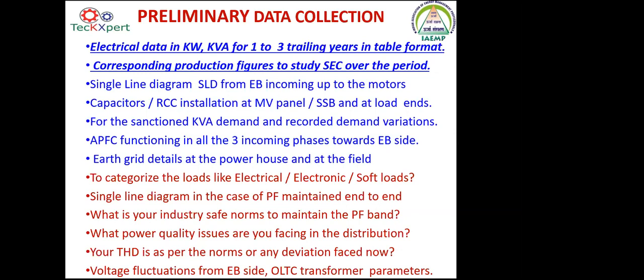Another aspect is, apart from the capacitors, the reactor-coupled capacitors installation, where it is done at the SSB, at the powerhouse, and what is done at the load end. At the load end, to be specific, the APFC functioning in all the incoming three phases is more important, because now the industry has gone to a slightly economical mode of 1 CT only. If they go for a 3 CT mode of measurement, especially in controlling the automatic power factor control, once you go for automatic power factor control, it has to be 3 CT operated. See, these are all the initial information available in the industry. This we have to discuss with the auditor.